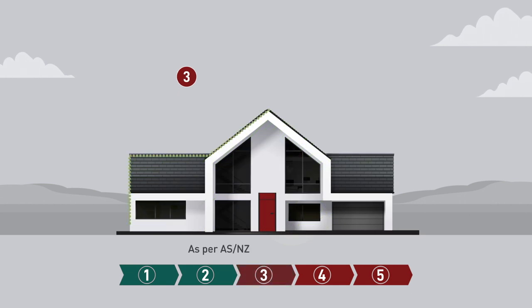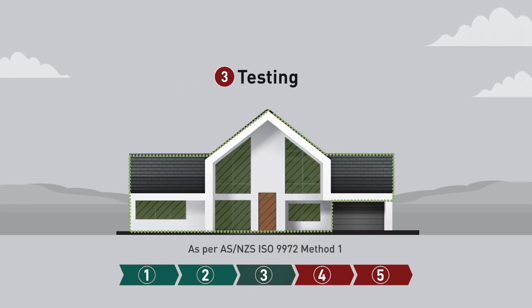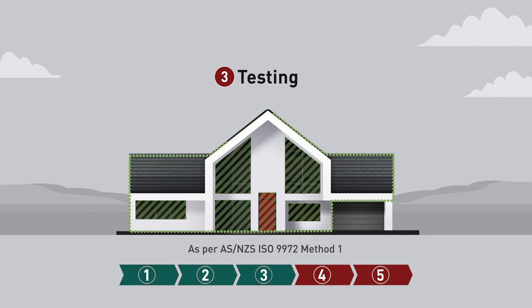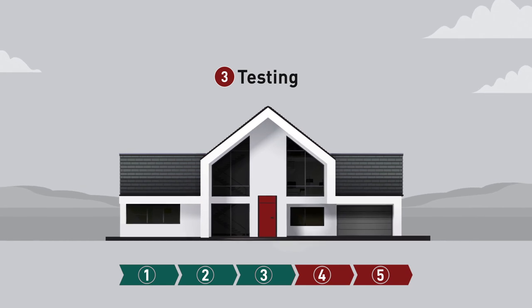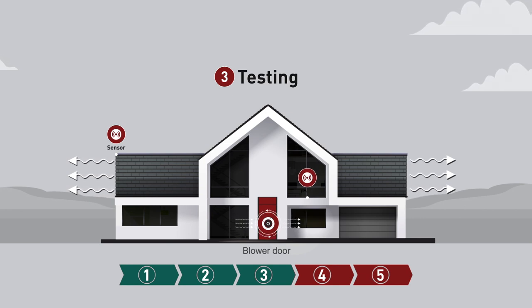Step 3: Testing. Firstly, prepare the house for testing. Close all windows, doors, trapdoors and ventilation and other openings. Blower door testing experts will then mount a blower door assembly at a door in the building envelope and connect pressure measuring devices to the inside and outside of the house.